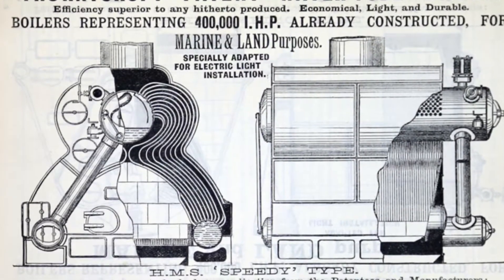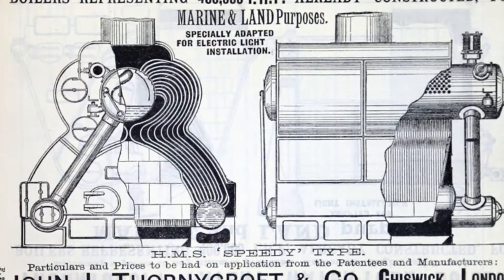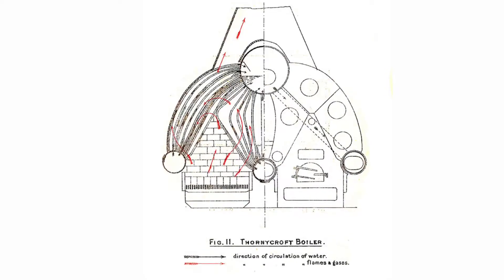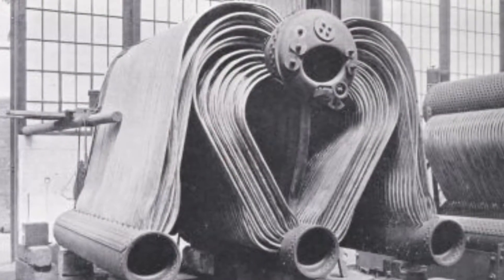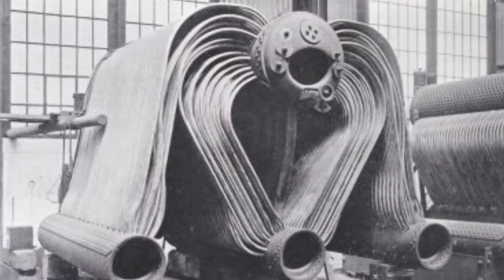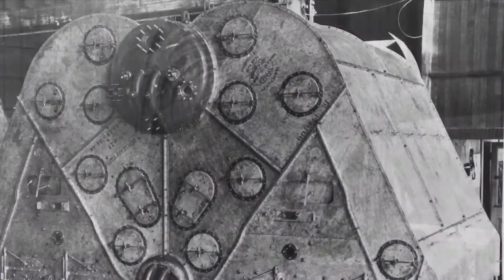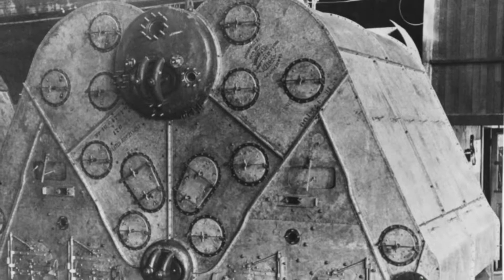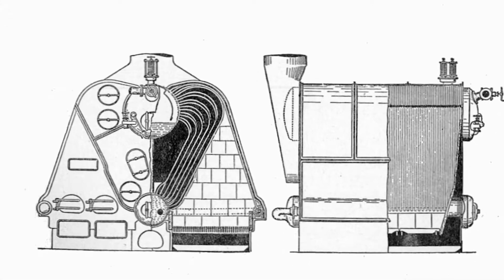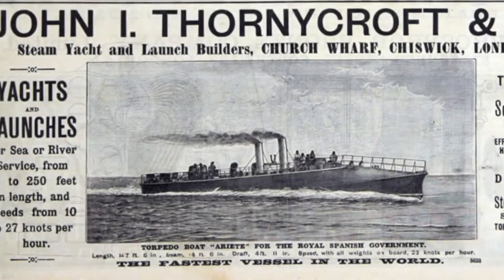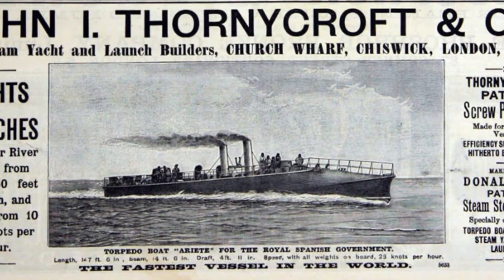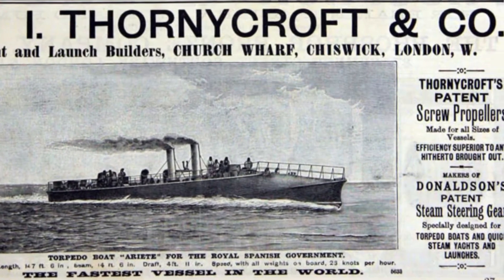Thornycroft Boiler: This boiler was designed by ship manufacturer John I. Thornycroft and Company. Its special design uses just one steam drum on the upper side with three downcomers arranged similar to an M-formation. However, due to several pipes having sharp bends, it carries a risk of leaking quickly — not only from potential thermal stress but also due to difficulties when cleaning. Because of these weaknesses, it was not as popular as the Yarrow boiler.